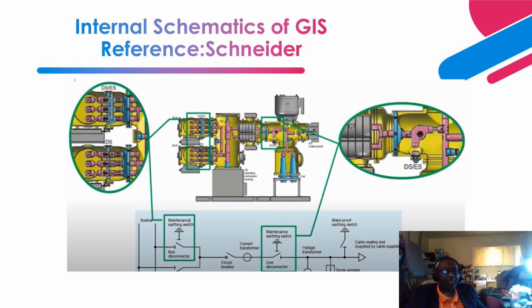Next, as you can see over here, the disconnector earth switches are basically the best access points to perform your testing. This is an indication: you see there's a window here that shows you the position and also how to access those earth switches. This is a typical maintenance switch that allows you to ground that switch, and if you want to perform testing, to remove that connection and connect whatever testing device you want to use.